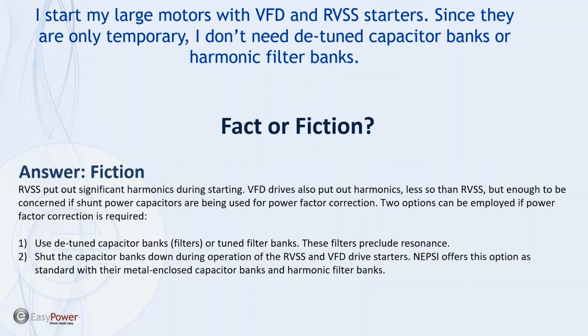So one thing that NEPSI does is put a fast trip into our control system, and we allow the VFD drive or the reduced voltage soft start to communicate, either through the network or through direct communication with an input to our control system, that it is about to start. We drop our system off, allow that VFD drive or reduced voltage soft start to start, and then the system comes back online and does its power factor correction after that motor start period. The other possibility is to just install detuned capacitor banks or tuned filter banks, your choice. But these two types of systems will avoid resonance in the network.